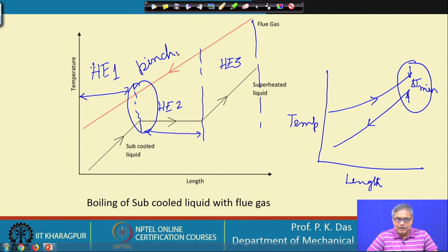So, this gives one restriction to the heat exchanger design, and this is happening inside the heat exchanger. This is very important and we have to maintain a pinch temperature. Probably I will elaborate this as we proceed, and that is how another complexity is added to your phase change heat exchanger. So, for a phase change heat exchanger, we have seen one unique feature: the minimum temperature difference between the two fluids can take place somewhere in between in the heat exchanger, particularly when subcooling or superheating or both are involved.